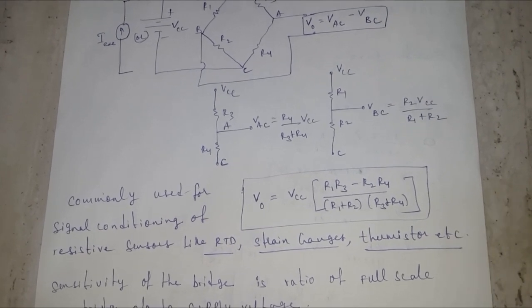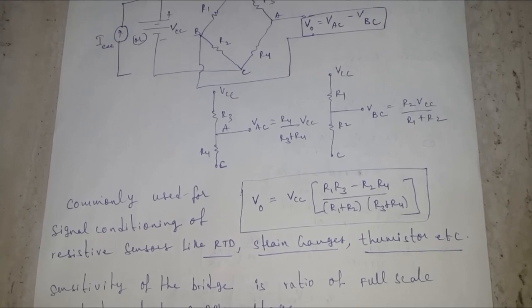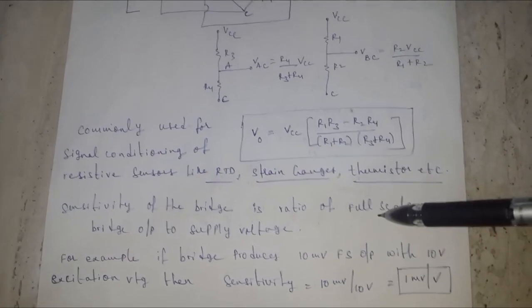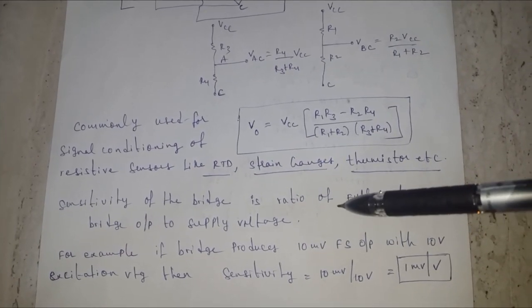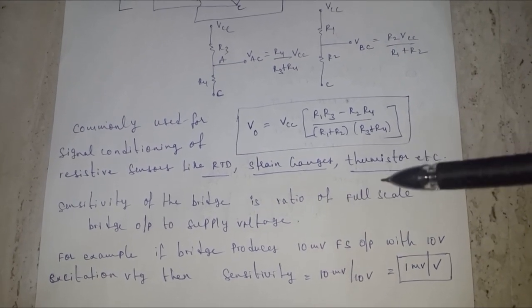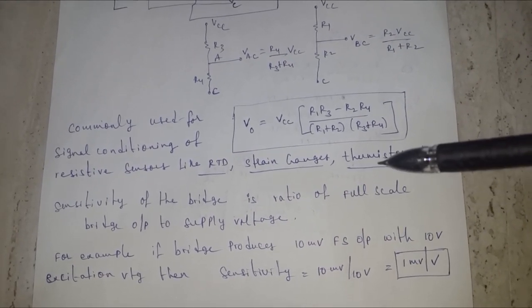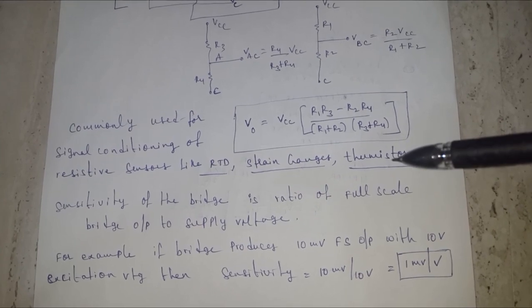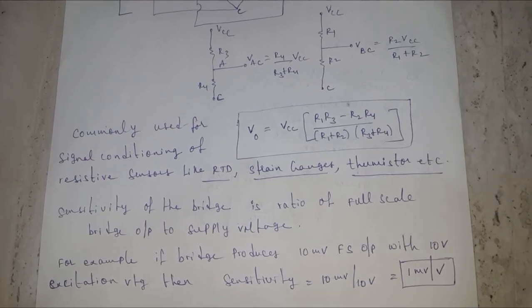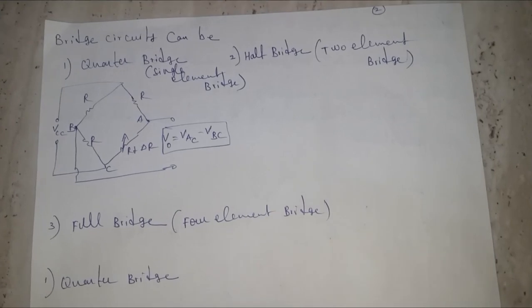It is used for resistive sensors like resistive temperature detectors (RTD), strain gauges for measurement of load and tension, and thermistors which are also temperature sensors. The sensitivity of this bridge is defined as the ratio of full-scale output to supply voltage. For example, if the bridge produces 10 millivolts full-scale output with 10 volts excitation, the sensitivity equals 10 mV / 10 V = 1 mV/V.